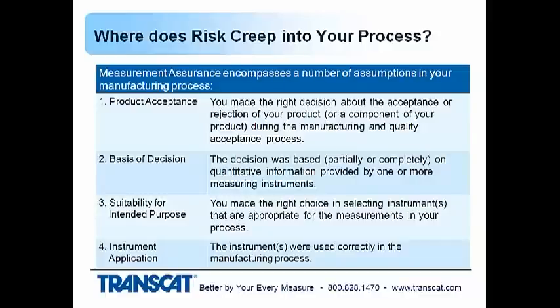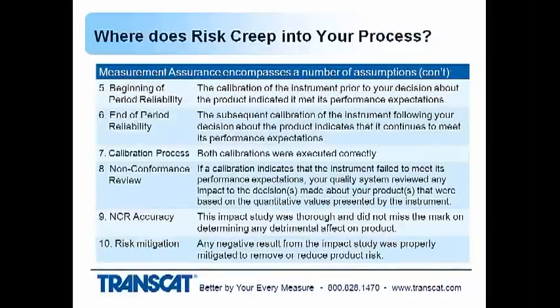Suitability for intended purpose is making sure that you've selected the right instruments for making those decisions about your product acceptance. Instrument application has to do with using the instrument correctly. You may have selected the right instrument, but are there things that you're doing that cause errors in the measurements? A term that I call beginning of period reliability, and that is the calibration of the instrument prior to using it in your production process. Does it meet its performance expectations prior to you putting it into place?